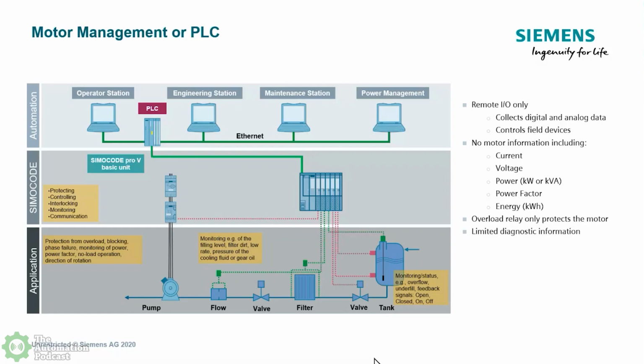We're just going to show you, as I stated, a standard across the line starter application. You can see here that we've got a flow, a valve, a filter, and we're measuring delta P across it. And then we have another valve, and then a tank with sensors for lower and upper, and also a float to tell where approximately the level is, and so forth. But this is just an application of a standard starter. And if you look at it, yes, it's an IEC starter. You can interject a NEMA starter here if you would like.